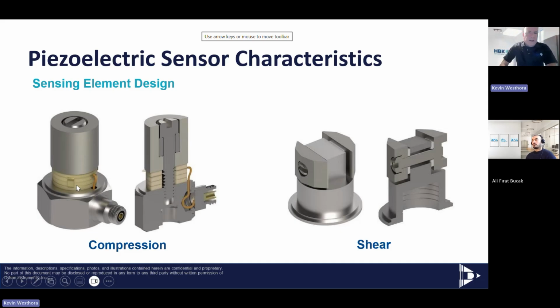And if you're looking at it on the output of an O-scope, the sensor looks like it's got full scale output with no vibration. That problem is called thermal transient response, and it's a very poor part of this design. The other issue is if I have any strain going on in the base of this accelerometer, that strain is going to be right in contact with the crystal, and it's going to give me an output error because of the strain, whether that strain is from a mechanical stress or from temperature changing.